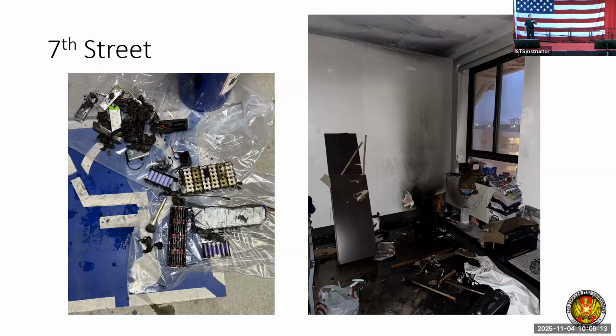It was in the corner, maybe 8 feet away, just like Dan showed in the videos. All this stuff we're talking about, the heat release rate, the thermal temperatures being brought into these rooms, activated the one sprinkler head. Looking at that picture, I would never anticipate a sprinkler head being activated unless it was directly over that burn scar. But it was about 6 feet away, and that sidewall head got activated and started working.